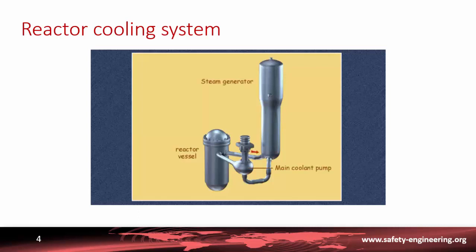The water leaves the reactor vessel through a large pipe called the hot leg and enters the steam generator. Here it is cooled by the secondary water, which is vaporized. It is then sucked into the intermediate leg by the main coolant pump and discharged into the reactor vessel through the cold leg.